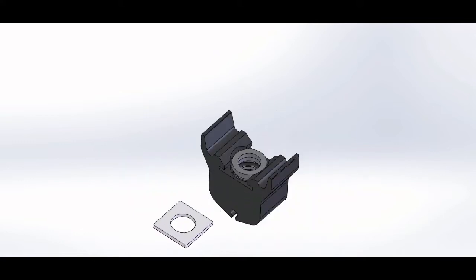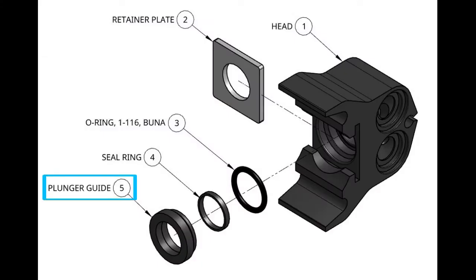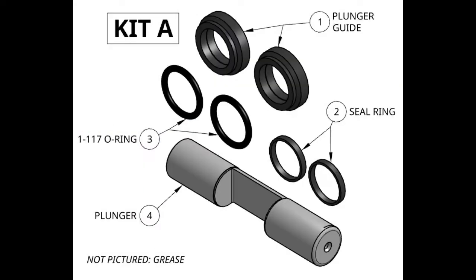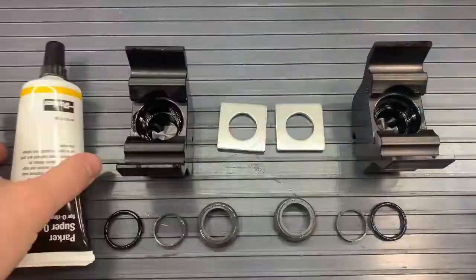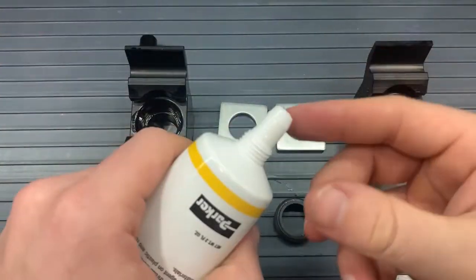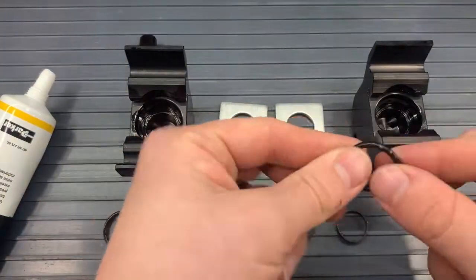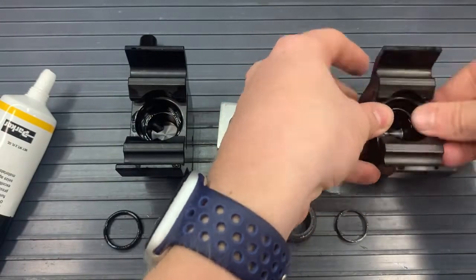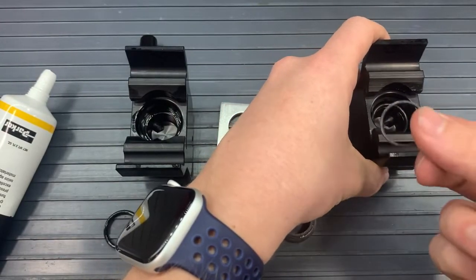With the heads off of the plunger, we can now remove the retainer plate. This should just slide off with your finger, as well as the 3 internal pieces inside that seal bore: the plunger guide, the seal ring, and the O-ring. Now we will grab kit A and replace the insides of the head. We will first take the grease and get a little bit on your fingers, just a little bit, and rub it around that O-ring. It should be the 1-116 O-ring, and we will put that O-ring inside the seal bore.